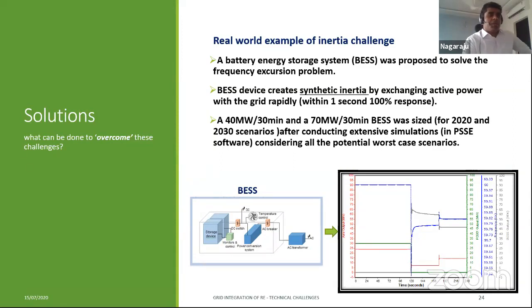So the response came after extensive simulations, considering all the worst case scenarios. One of the worst case scenarios is when there is already cloud cover on a PV farm, and at the same time, one of the gas turbines trips. That is the worst case that the grid can see. It can happen in other cases, but in terms of N-1 security or N-2 security, that is the worst case the grid operator needs to maintain.